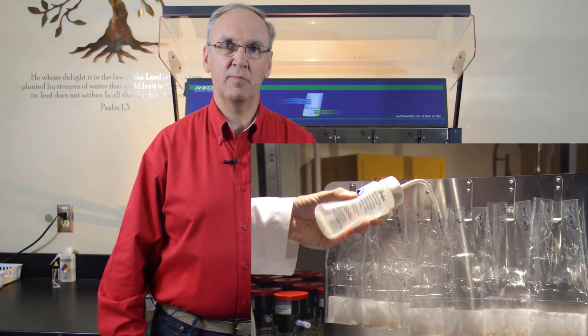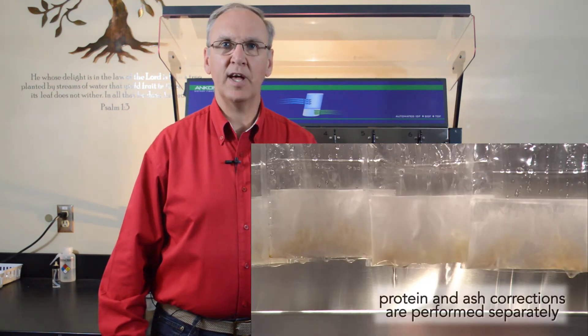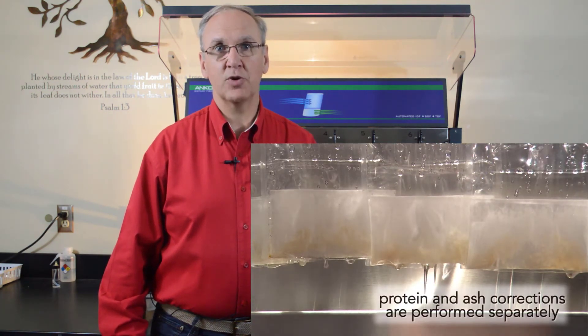When the process is complete, the samples are removed, rinsed with acetone as per the method, dried, and reweighed. Ash and protein corrections are determined as with the conventional method, and results are calculated.